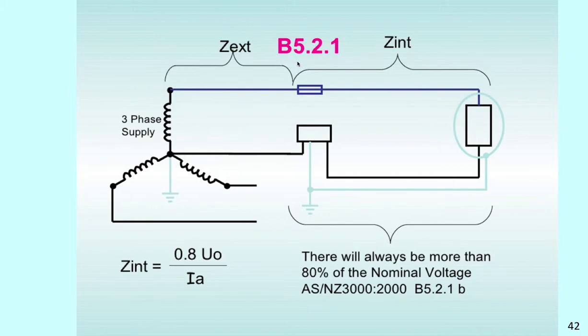Using table B5.2.1. Again, to summarize. We have Z or impedance external. And we have impedance internal. Basically, we have no control over the impedance external. And normally the supply authority will provide information of what they expect the impedance to be at the point of supply. And then after that, it's up to you as the electrician to calculate the internal impedance and work out the final fault loop current.